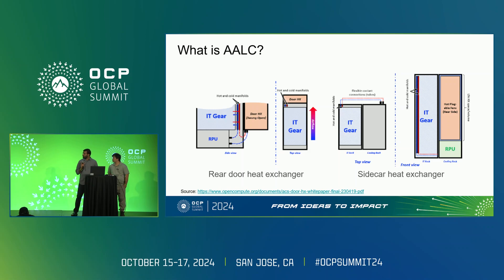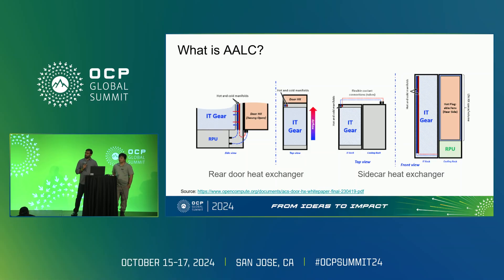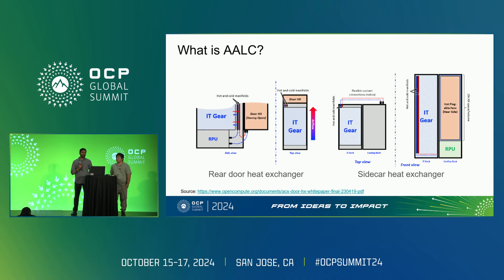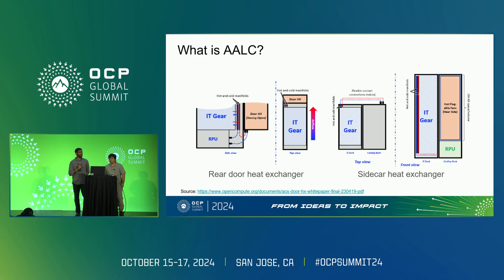As you see on the left side, you have a rear door heat exchanger where the heat exchanger is on the back of the server rack, taking the air from servers and cooling the liquid from the IT hardware, in turn releasing that heat to the facility air. Whereas in Sidecar, your heat exchanger is next to the IT rack, giving you more space, which comes with more capacity to handle higher heat loads.